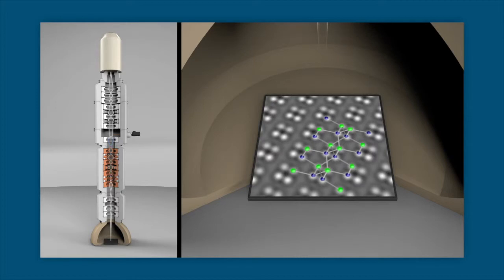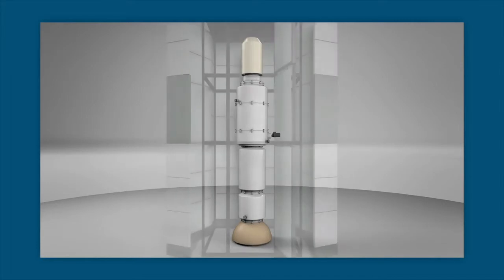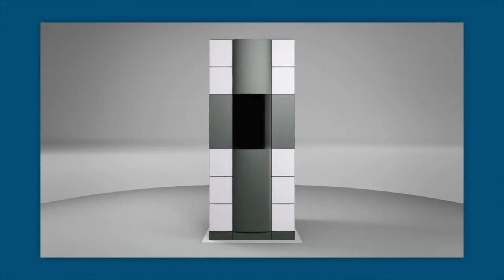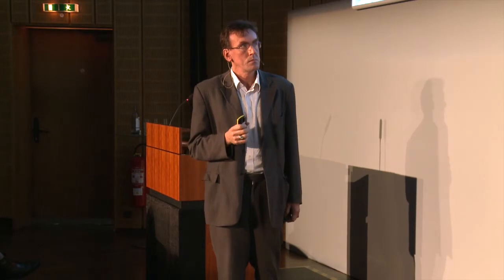These advances in electron microscopy are real breakthroughs. They also impose quite strict requirements on the stability of the microscope column, on the stability of the frame around the microscope, and on the stability of the building that houses it. Some of these improvements become apparent if we look at how images acquired with transmission electron microscopy have evolved over the last 15 or 20 years.